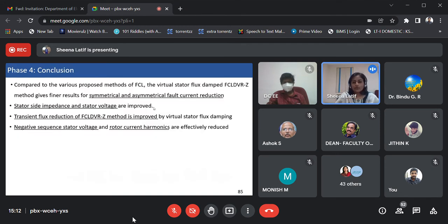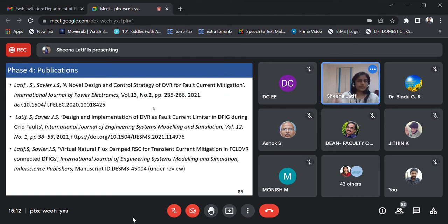So as a conclusion of this phase, compared to the previous methods of fault current reduction that we have suggested as part of our research, the FCL DVR impedance and virtual stator flux damped method is getting finer results for symmetrical and asymmetrical fault current reduction, with stator side impedance and stator voltage improved. And the transient flux reduction of the FCL DVR impedance method reduces the transient overcurrent conditions also. These are the publications of this phase.